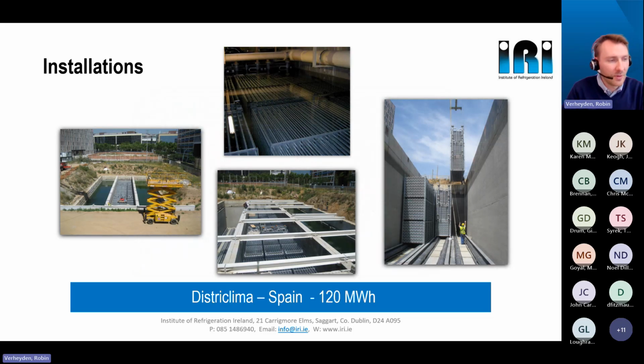That's a very important point. In the previous slides, you saw drawings with complete ice tanks, the coil into a tank. But for bigger applications, what we actually see is coils stacked on each other and lifted into a concrete tank. This allows much higher storage capacities in a small footprint. To give you an indication, you see a lot of coils in three separate concrete basins, and afterward they close it up and make a nice piece of nature in the middle of Barcelona's center.